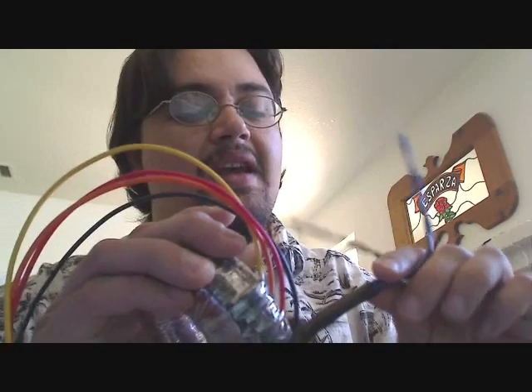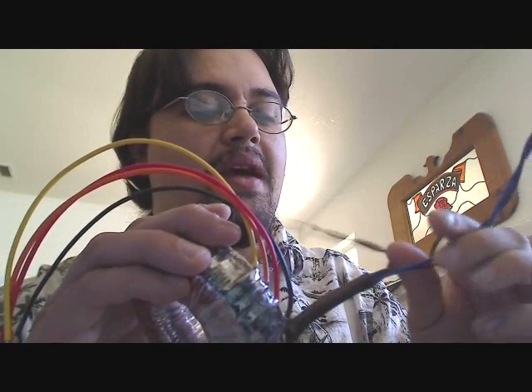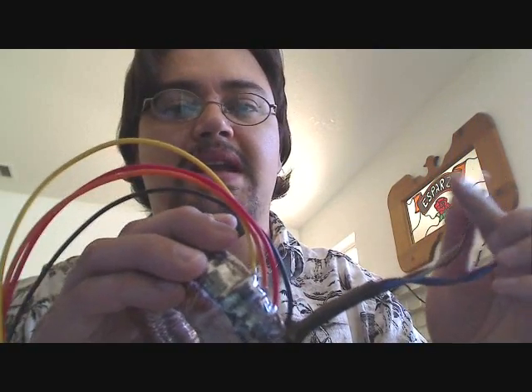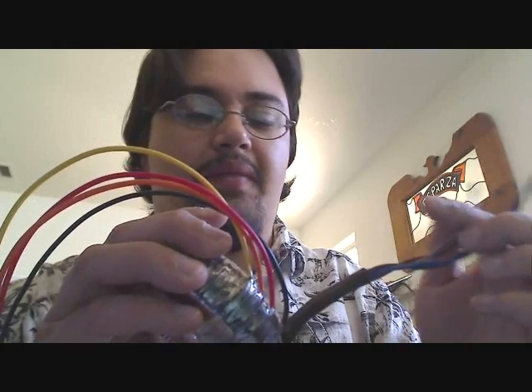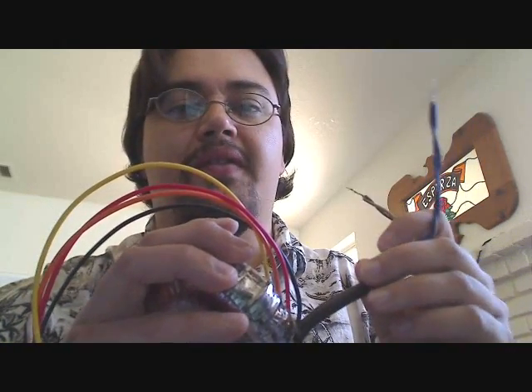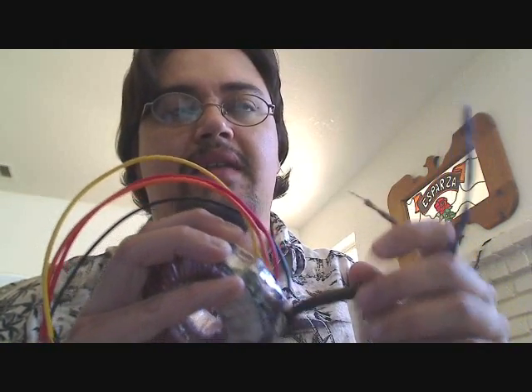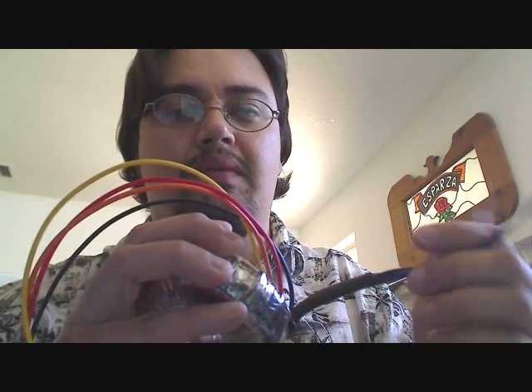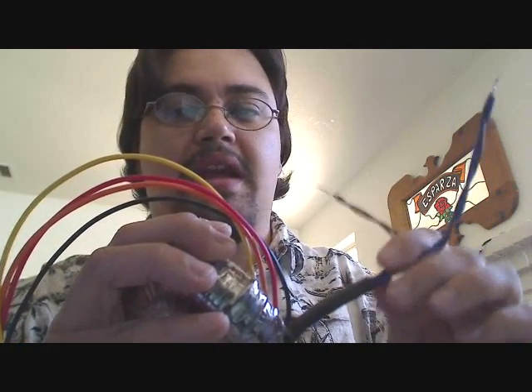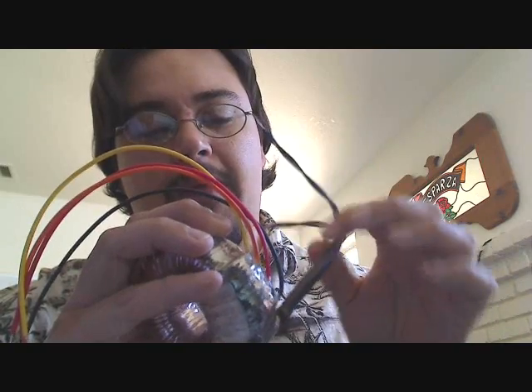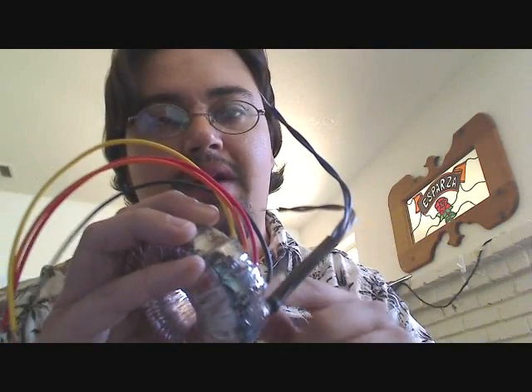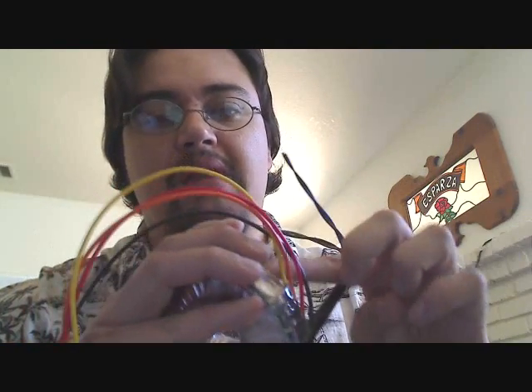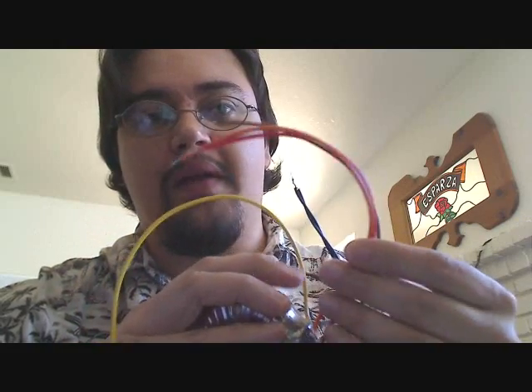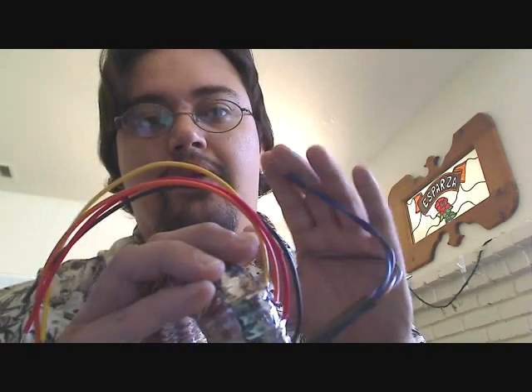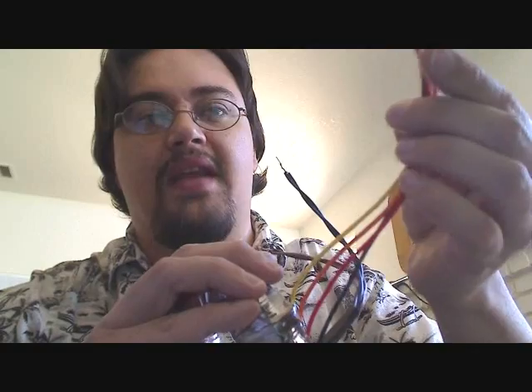If you live in countries that don't use that standard and need something closer to 230 volts, you wire your primary windings in series and still leave your secondary windings in parallel, so you can have 230 in and 12 AC out.